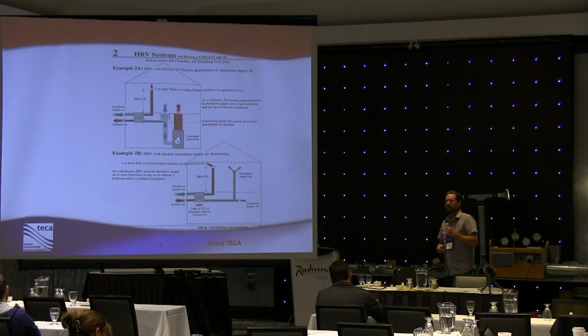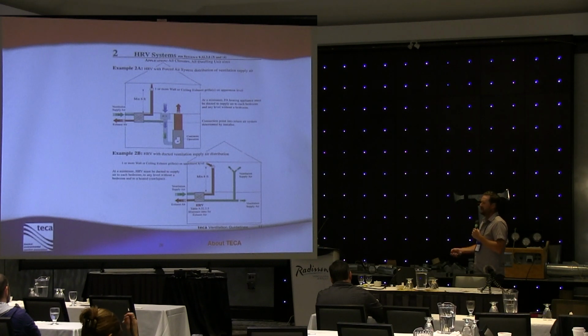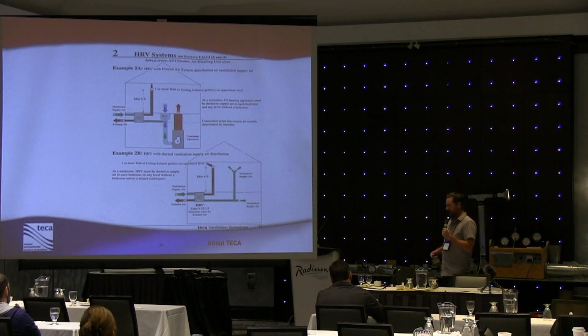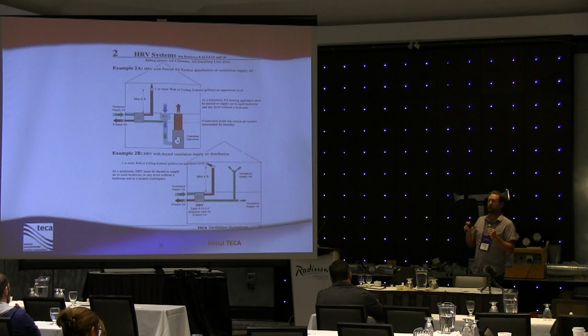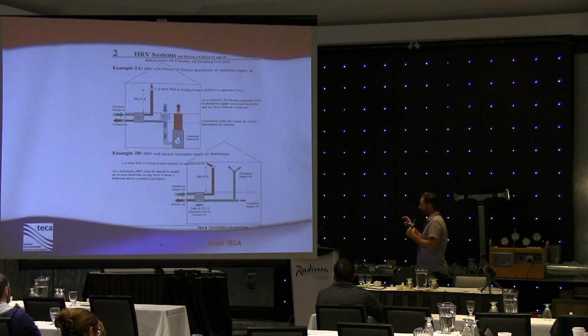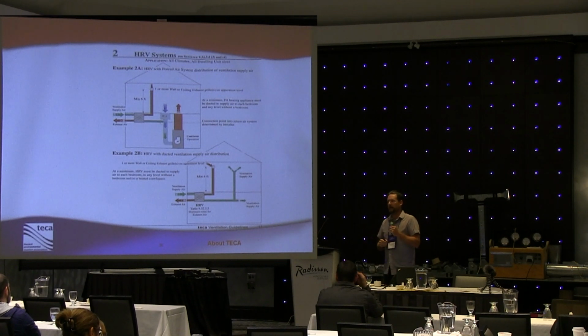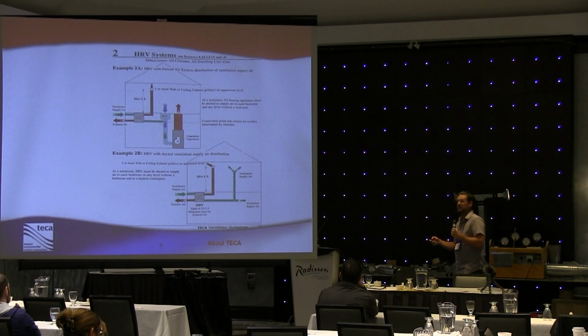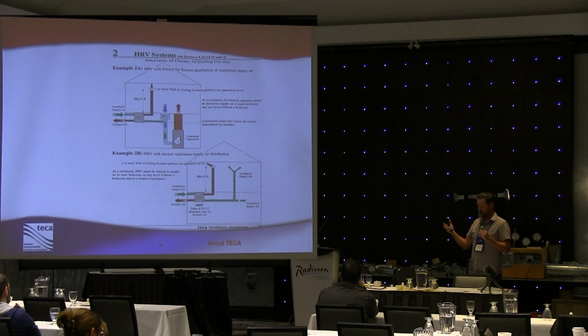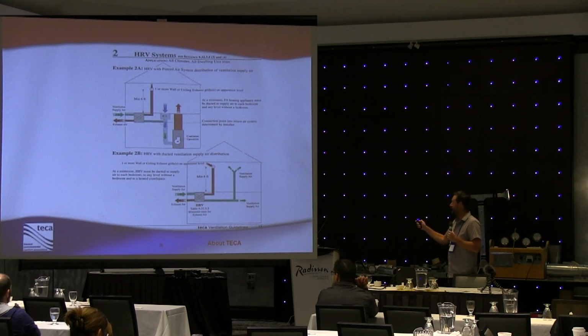Not every building is perfectly suited for an ERV. ERVs and HRVs are very unique in the way they operate. If you need to dehumidify, you should stick with an HRV. If humidity is not such a problem, or if you want to maintain a certain level of humidity inside of a building, ERV is maybe a little bit better way to go. Buildings with lots of wood builds. If you've got a lot of interior trims or wood floors, cabinets, wall finishes, we like to keep a little bit more moisture inside those buildings, so an ERV may be a better fit. Talk to your ventilation contractor.